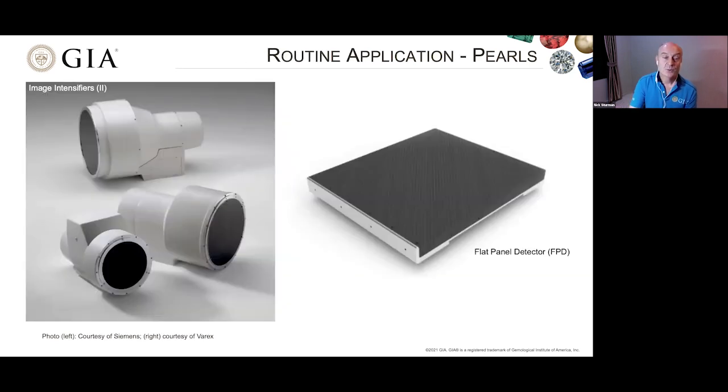Another point we have to cover as far as the X-ray machine, as I said, it's made of many parts, is the detectors. So we have two types shown here, the image intensifier and the flat panel detector. So here's the image intensifier, and this is the flat panel. The image intensifiers are generally being phased out when it comes to finer detail imagery, as they are more grainy due to the difference in pixel sizes and sensitivity. The flat panel detectors are now more or less the norm.